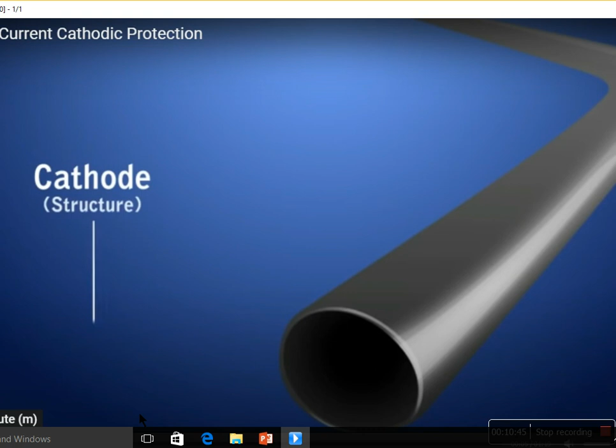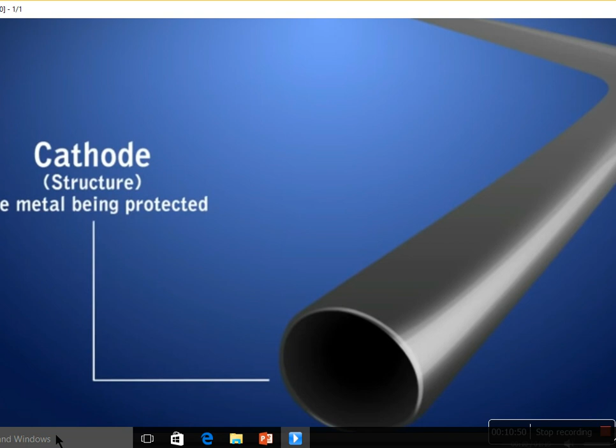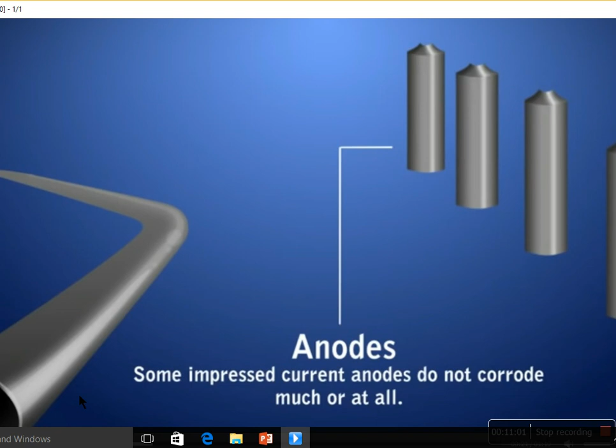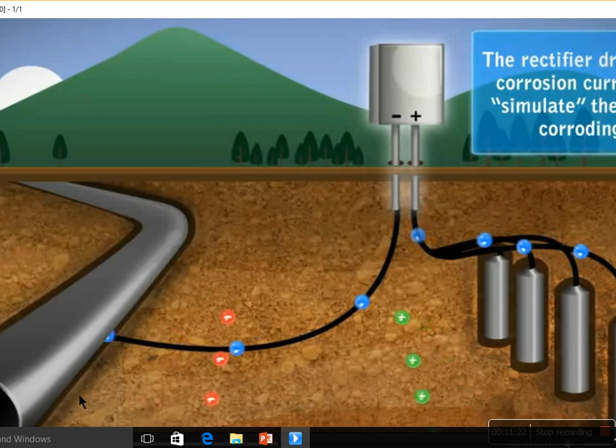Let us see one animation of the impressed current protection method, as we saw in earlier slides. This is the underground pipeline structure which is made cathodic, and we are going to prevent it from corrosion. These are the different anodes, and these anodes are connected underground using a DC power source, that is a rectifier. This rectifier will supply DC current, and it drives the corrosion current to simulate the anode corroding.